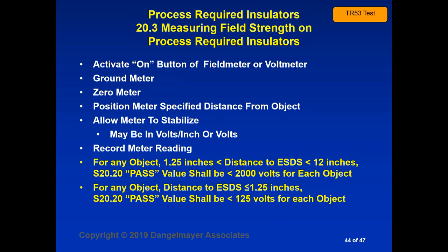125 volts at 1.25 inches is okay. That's clear. However, the first statement says that if I had 2,000 volts at 1.5 inches, that would also be okay. Does not compute. If something is sensitive to 125 volts at 1.25 inches, certainly it's going to be hazardous to have 2,000 volts at 1.5 inches. And that's what this particular specification in S20.20 leaves in doubt.